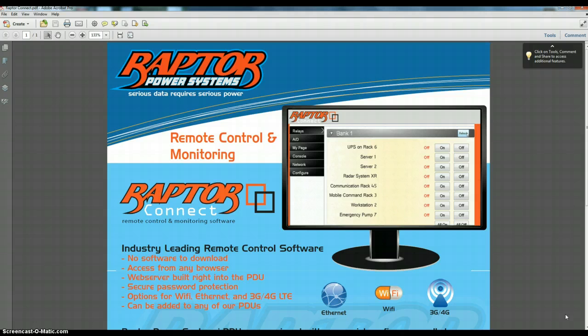Raptor Connect is a proprietary software package used on our power distribution units and frequency converters from 1 kVA up to 10 kVA. Anything above 10 kVA uses different software. It monitors temperature, volts, and amps, and lets you remotely turn power on and off. There's no software to download, and you can access it from any browser since it has a web server built directly into the PDU, eliminating compatibility issues. There's secure password protection, with options for Wi-Fi, Ethernet, and 3G, 4G connections.